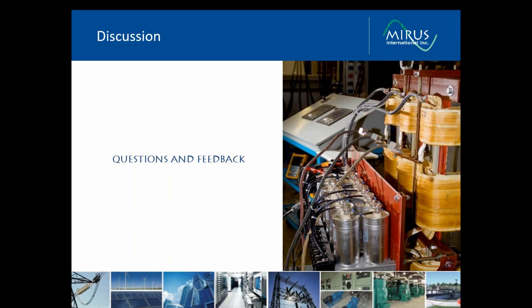Another question. Can you please elaborate on how active front-end drives introduce high-frequency harmonics and why that is a problem? So I did touch on that in the presentation. The main issue here is that the active devices, whether they be active front ends or an active harmonic filter, require IGBTs to operate. And these IGBTs are fast switches. And as they switch at their switching frequency, they will introduce harmonics into the power system. These need to be filtered. They need to be filtered with a passive filter device, just the same way the lower frequency harmonics introduced by six pulse drives need to be filtered.